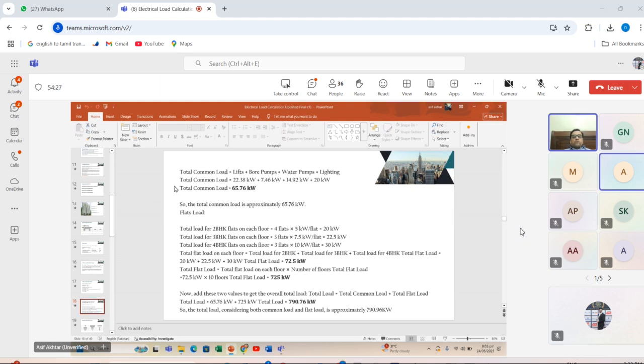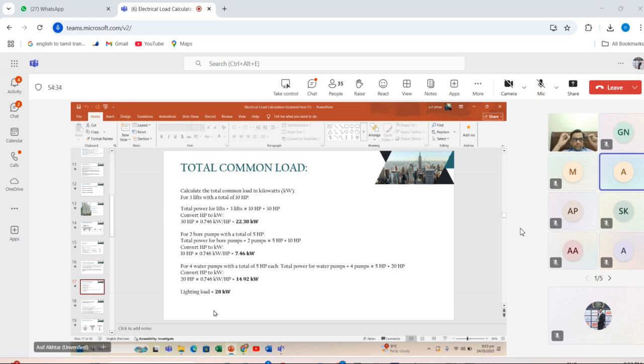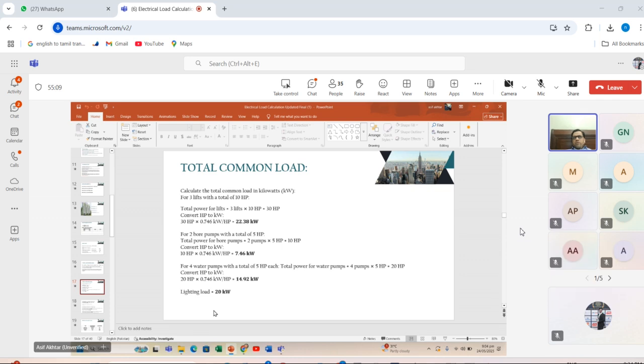Now I have a question. For the common load, how did we calculate the lighting load in a high-rise building? How do we calculate the lighting load for the common areas, whether it is calculated per square foot or by the footfall of the people living there? Is there any specific formula for that? Both, it depends upon the building size. Just for your understanding I have added 20 kilowatt. The 20 kilowatt will include the parking area, lobby area, and staircase area. If you add all these things, it will be approximately 10 kilowatt to 15 kilowatt. It depends upon the building size; it can increase or decrease.